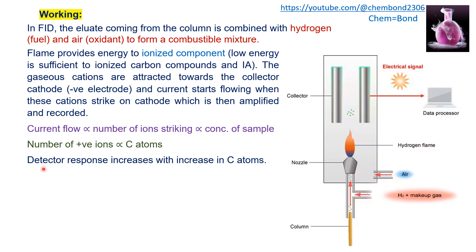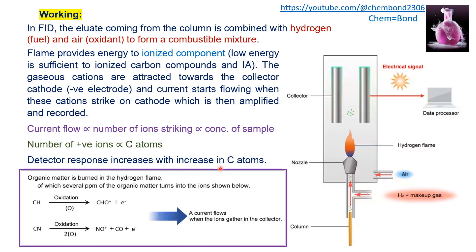The detector response increases with an increase in carbon atoms. The organic matter is burned in the hydrogen flame, and several ppm of organic matter is burned into ions. For a hydrocarbon mixture, combustion produces cations and electrons. For carbon-containing nitrogen compounds, combustion produces cations, carbon monoxide, and electrons. These cations move towards the collector electrode and are amplified.